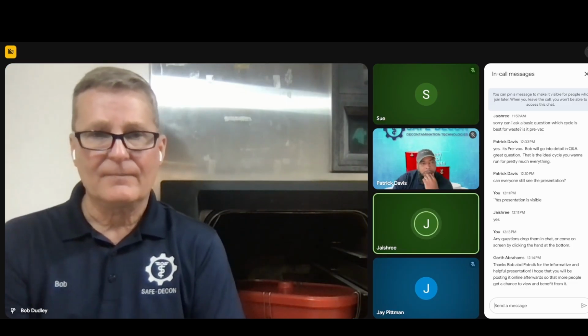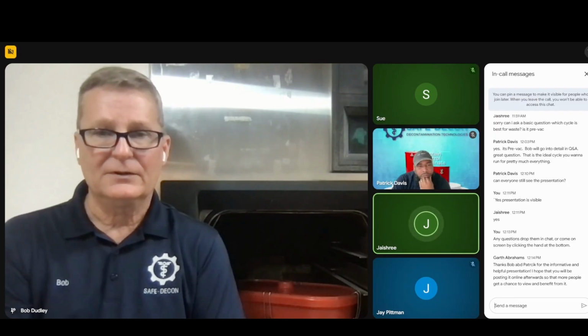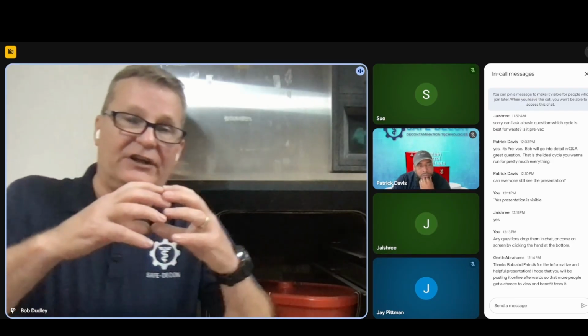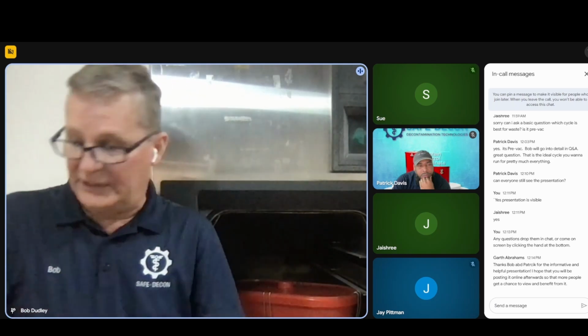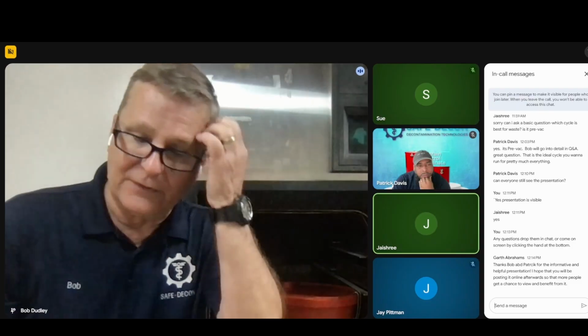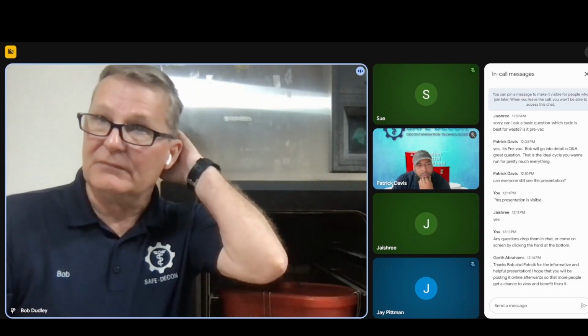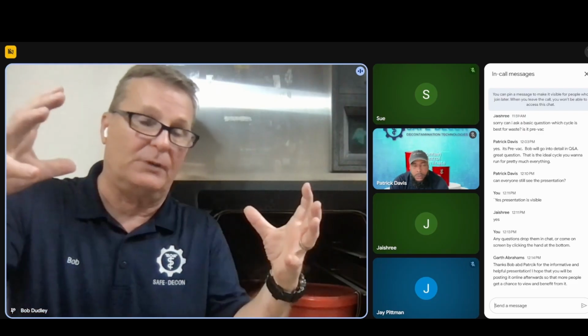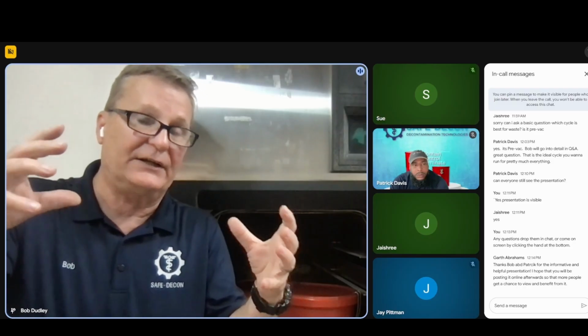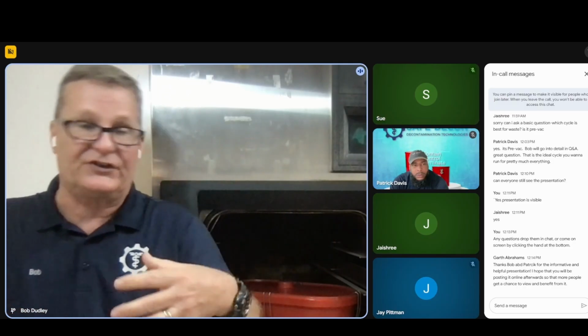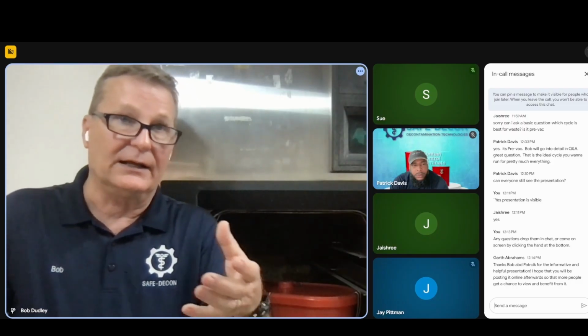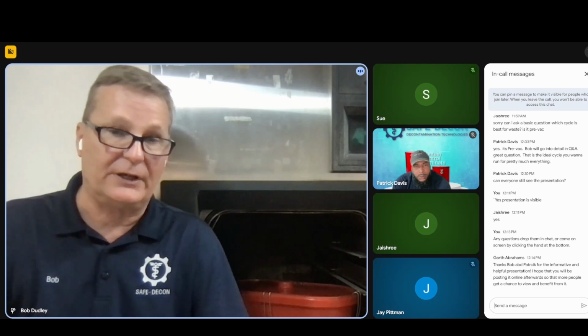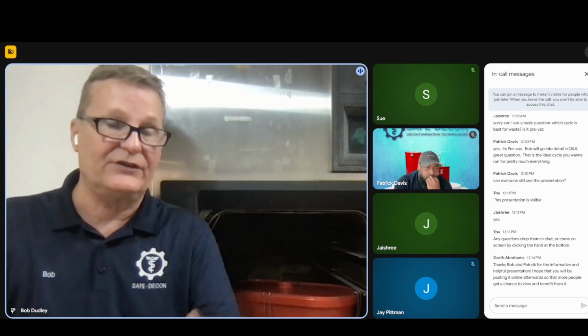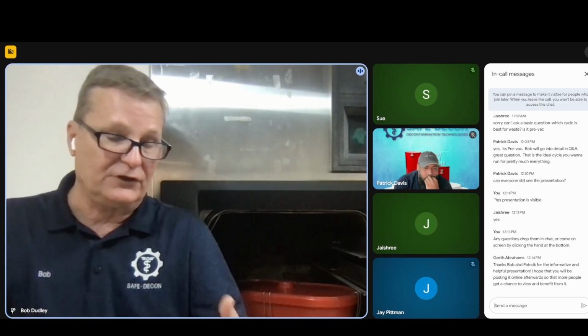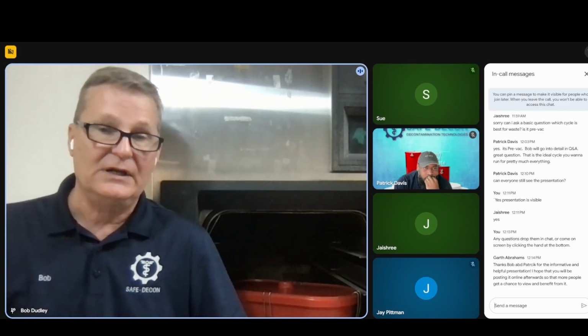So then you're saying that to the end of the cycle, we get a collapsed closed bag because of the cycle. It'll close, yeah. As it expands, then at the end of the cycle, it's going to look like a crumpled, wrinkled mess. Yeah. And that's why I showed you in that one picture. I wanted everybody to see that, like the one bag, it just remained the sealed wet bag. It just blew up like a balloon, and it didn't burst. That cycle did fail, even though it did have the water. It did show that it got the steam and the heat according to the chemical strips. But the biological, which is the ultimate way to test whether you have gotten the kill on something, is that biological.